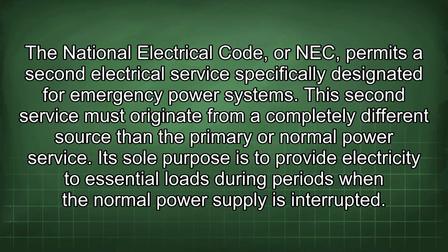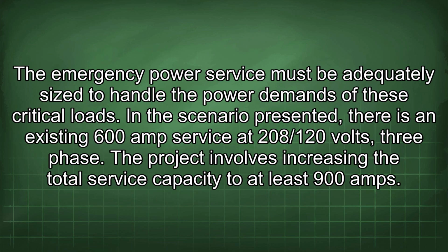The National Electrical Code, or NEC, permits a second electrical service specifically designated for emergency power systems. This second service must originate from a completely different source than the primary or normal power service. Its sole purpose is to provide electricity to essential loads during periods when the normal power supply is interrupted. The emergency power service must be adequately sized to handle the power demands of these critical loads.